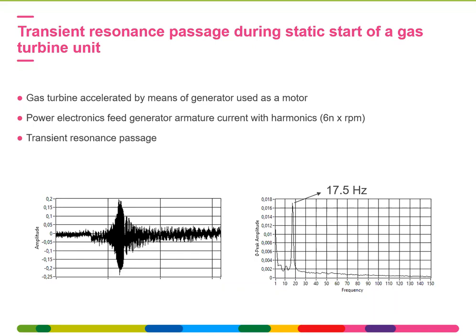Dynamically here, you can see, for instance, that during a start of the gas turbine, where you use the generator as a motor, you will excite torsional vibrations, because the power electronics that you use to run the generator as a motor feed the generator armature current with harmonics. As you can see on the bottom left picture, you're actually going through a transient resonance where you excite the lowest torsional natural frequency, which is around 17.5 hertz. You pass it fast enough, so there's no issue, but this is already useful to validate the model, for instance, prior to synchronizing to grid.